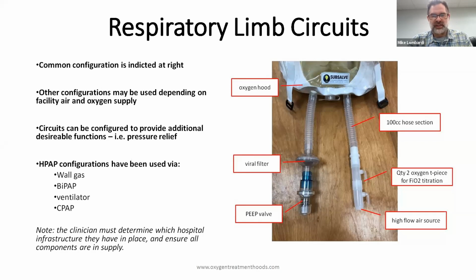On the expiratory side, there is a viral filter, and that's probably the most important from the COVID standpoint, because with this method of non-invasive ventilation, in addition to providing positive pressure and higher FiO2s for the patient, all of the gas that passes through the patient's environment goes through a filter. So that adds an additional layer of protection for the healthcare workers. Below the viral filter, you'll see a PEEP valve, and that's where we're able to regulate the pressure inside the hood. So this is one example of a circuit.